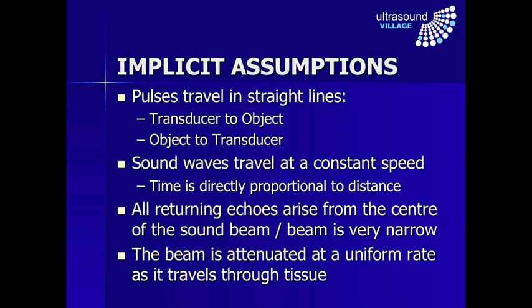But there are some implicit assumptions the machine makes. It assumes that pulses travel in straight lines — the pulse goes directly from the transducer to the object, reflects, and travels straight back. The machine assumes sound waves travel at a constant speed, which is how it determines how far an object is from the transducer by measuring the time taken for the pulse to travel there and back. It also assumes that all returning echoes arise from the center of the sound beam — or alternatively that the beam is very narrow. Finally, the machine assumes that the sound wave is attenuated at a uniform rate as it travels through the tissue.